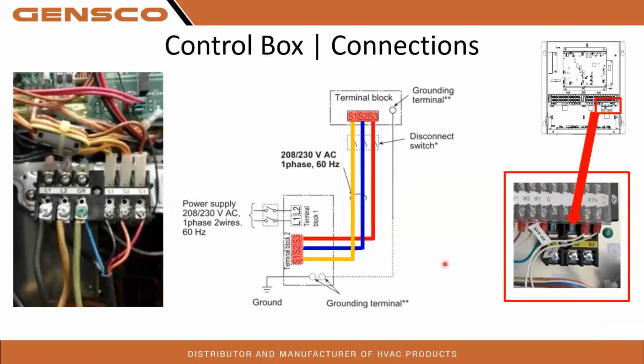All right, and here we have our connection diagram for the S1, S2, S3, so your power and communication from the heat pump to the indoor coil. Nothing's really changed on this from the other M&P product series. You're going to want to make sure to use a 14/3 stranded shielded on this if possible.